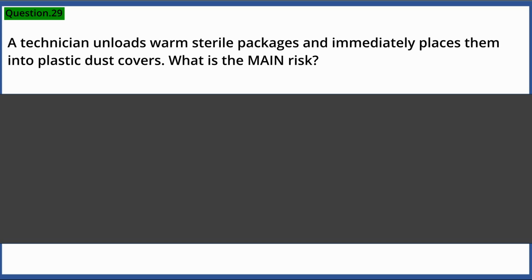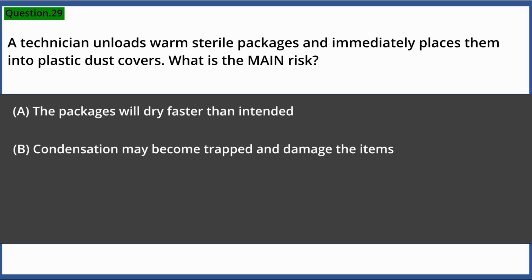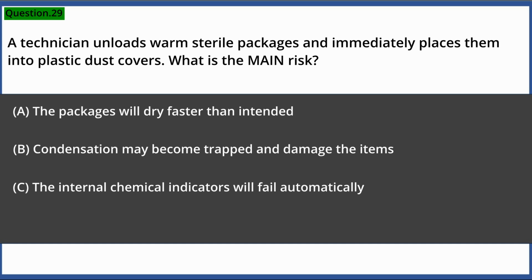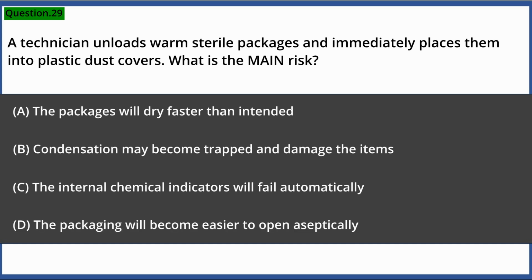A technician unloads warm sterile packages and immediately places them into plastic dust covers. What is the main risk? A. The packages will dry faster than intended. B. Condensation may become trapped and damage the items. C. The internal chemical indicators will fail automatically. D. The packaging will become easier to open aseptically. Answer: B. Condensation may become trapped and damage the items.